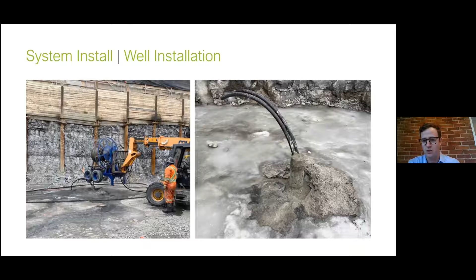That bentonite helps anchor the piping within the borehole, and it also improves the thermal efficiency of how it interacts with the bedrock and surrounding area. All of that bentonite is mixed on site from dry mix bags, using equipment similar to what's used for shotcrete on a swimming pool. The photo on the right shows a completed wellhead, with a small steel casing filled to the top with bentonite. That casing is removed once the bentonite's solidified, just before connection to the horizontal geothermal loop.